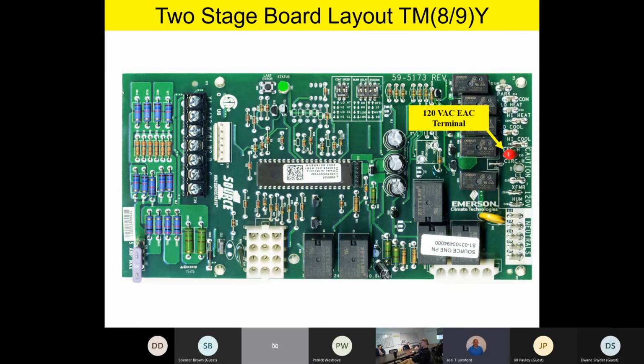So as we come down on the right-hand side of the board, we have a 120-volt output for an EAC. That's for an electronic air cleaner. Anytime the fan is running, that terminal will be energized with 120 volts for an electronic air cleaner if so desired. You'll notice we put a little red rubber ball on there just to remind you that it is high voltage, and it does not come from the factory with anything hooked up to it. That's why we put that little insulator ball on there for safety. But if you remove that, you'll find a terminal underneath that you can hook up for an electronic air cleaner anytime the fan is running, if so desired.